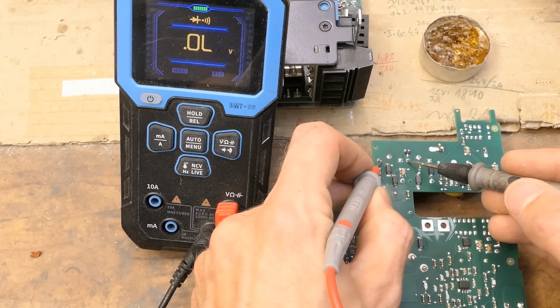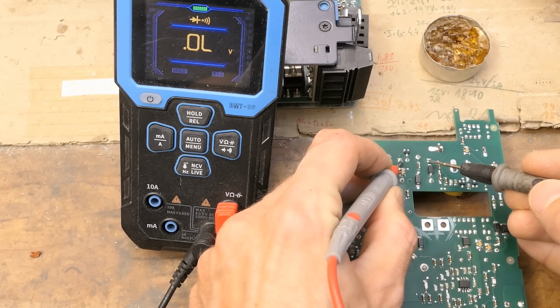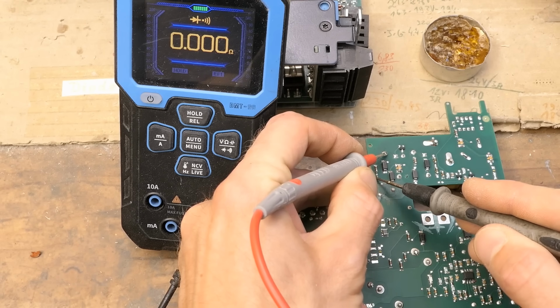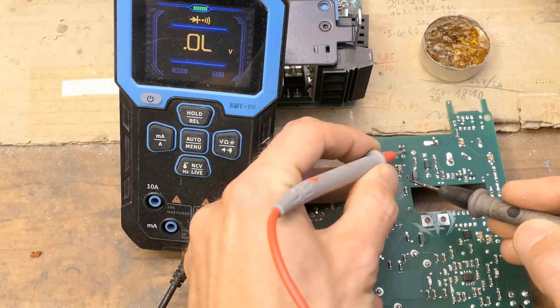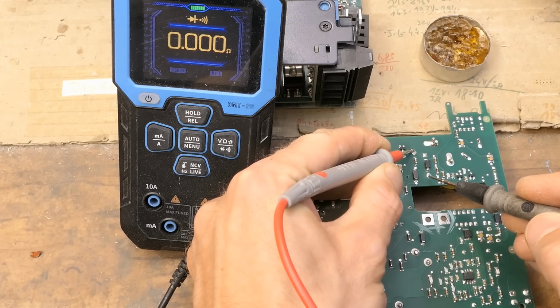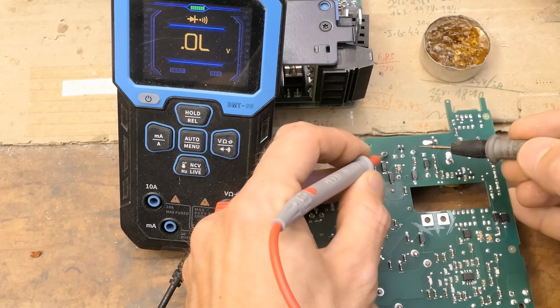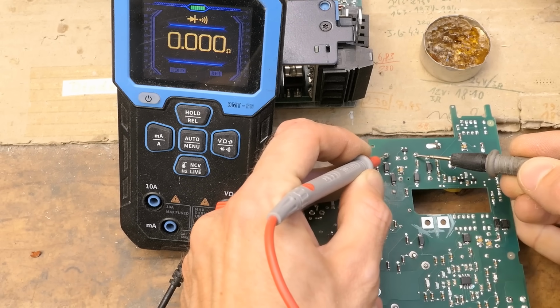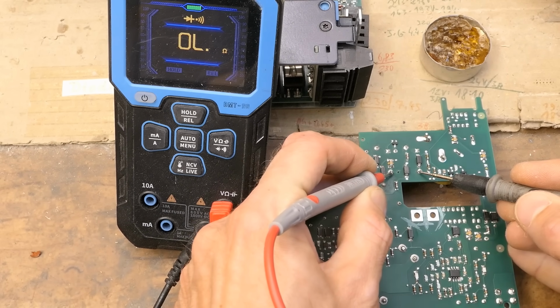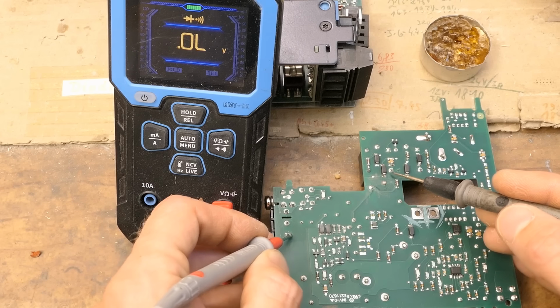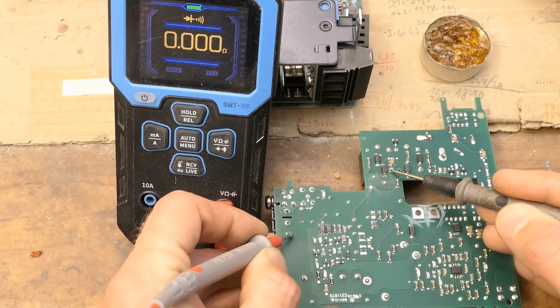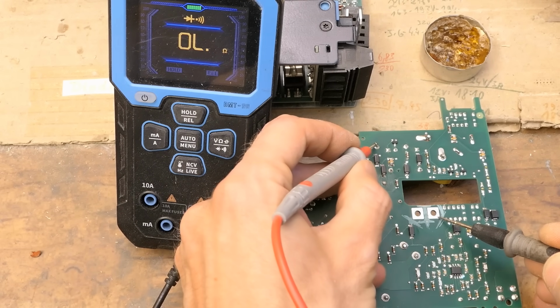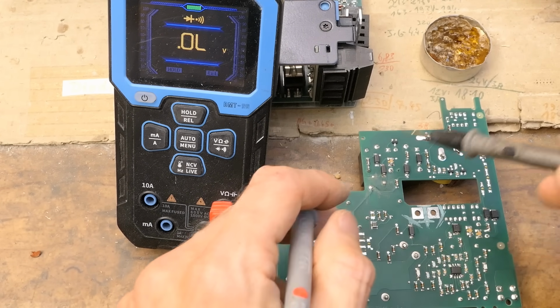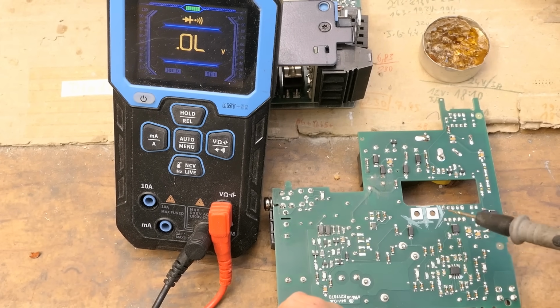There are the two 12 volt relays. It seems the coils are in parallel. This is the normally closed contact, normally open, normally closed, normally open. Now the common contacts are actually common for both relays, and the normally open ones are also common. The neutral goes to the normally open contacts, and this terminal goes to the common contacts, which means basically the relays bypass the neutral to this.